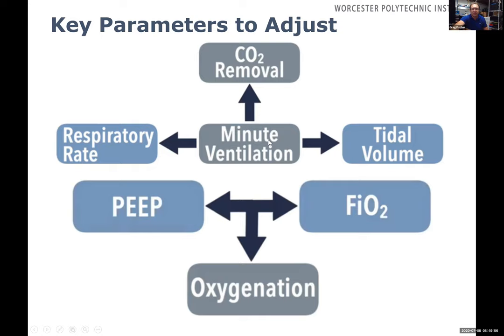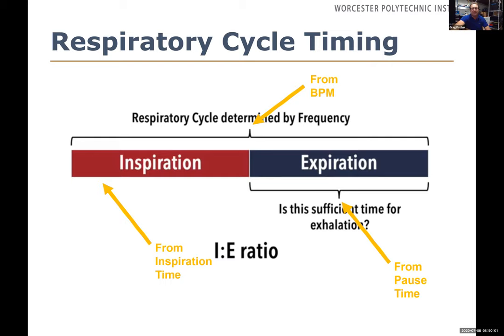There are really three parameters you want to adjust but only two can be set independently — the third follows. You control how much time to inhale, how much time to exhale, and how fast to repeat the cycle. These are dependent on the patient and the mechanical properties of the lung.